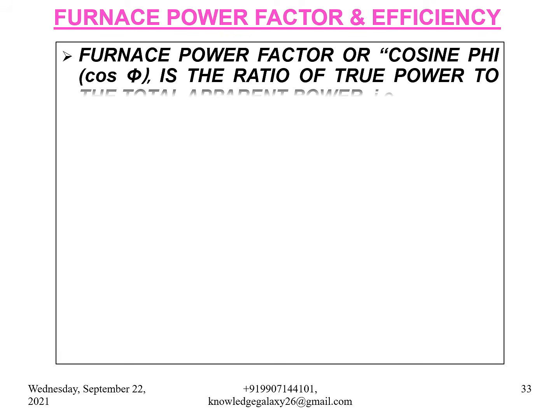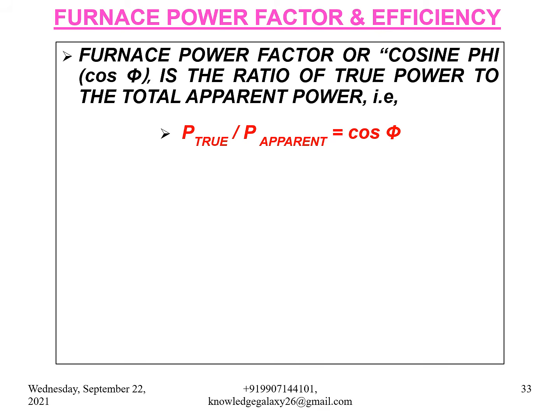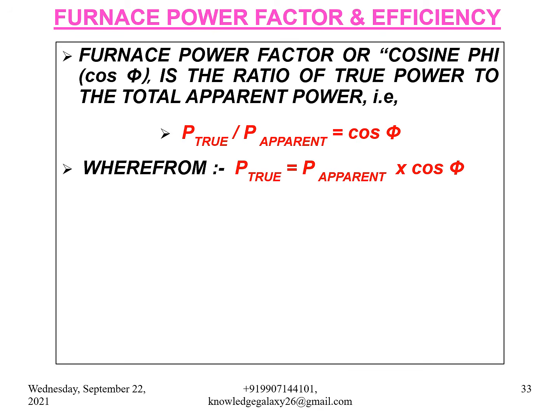Furnace power factor and efficiency. My dear friends, this is another very important parameter from the point of view of efficient power utilization and productivity improvement. Furnace power factor, or cosine phi, cos phi, is the ratio of true power to the total apparent power. That is, P true divided by P apparent is equal to cos phi, whence P true is equal to P apparent times cos phi.